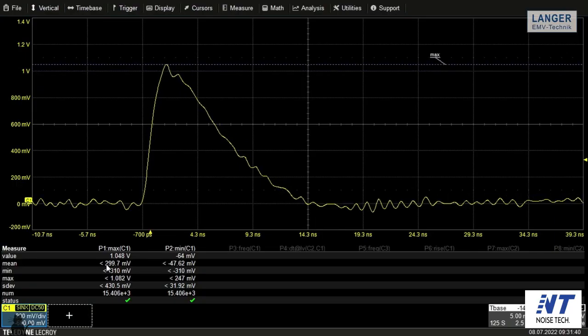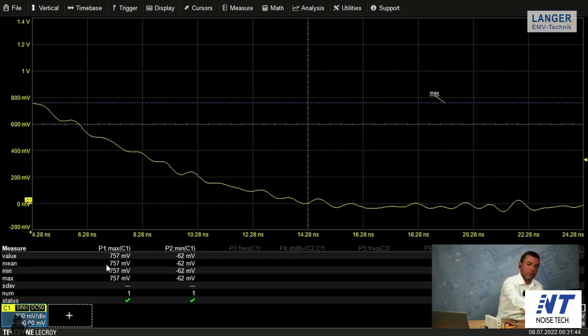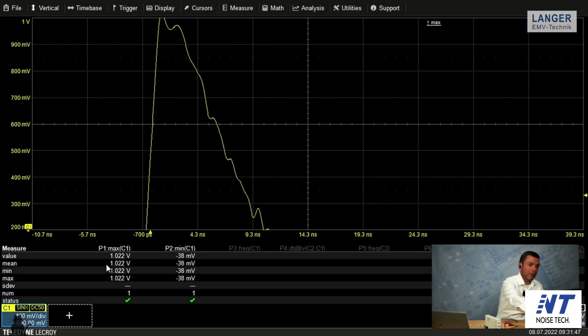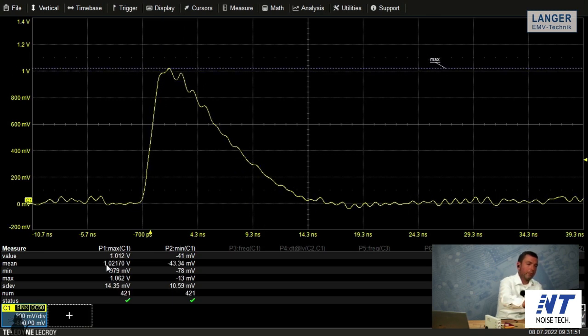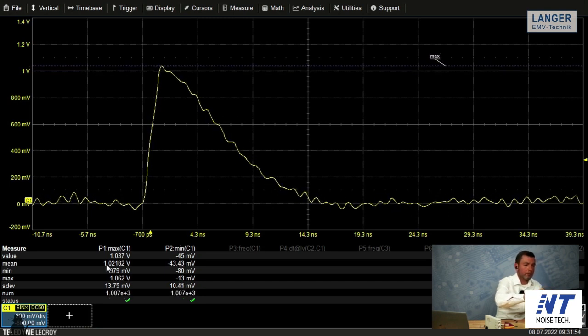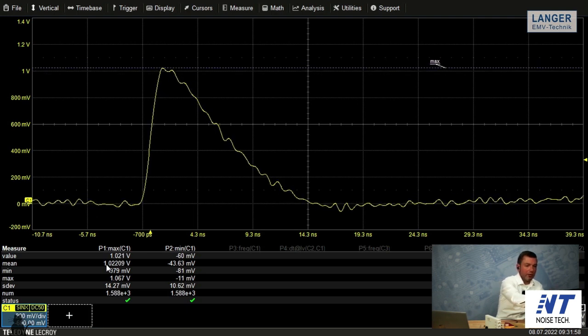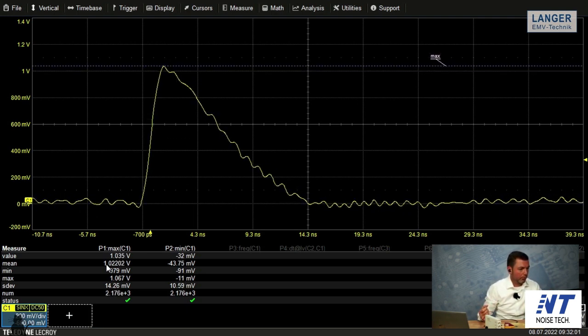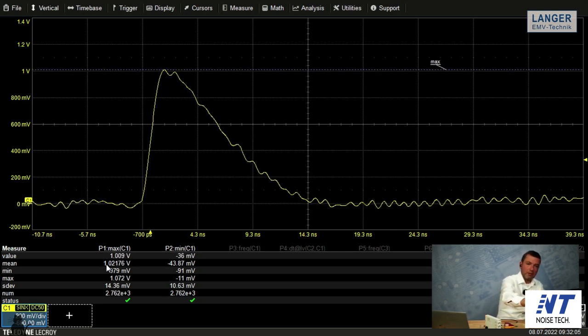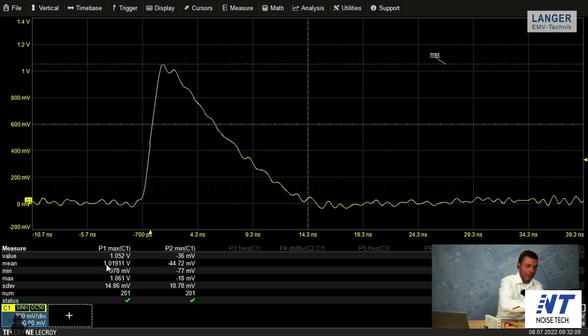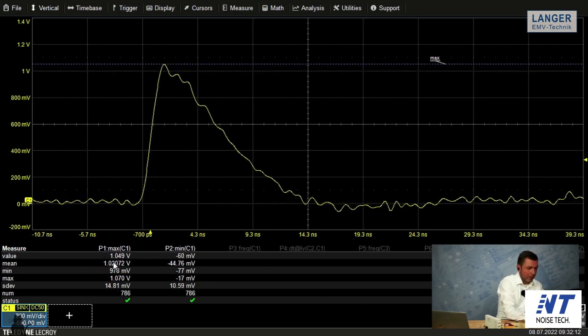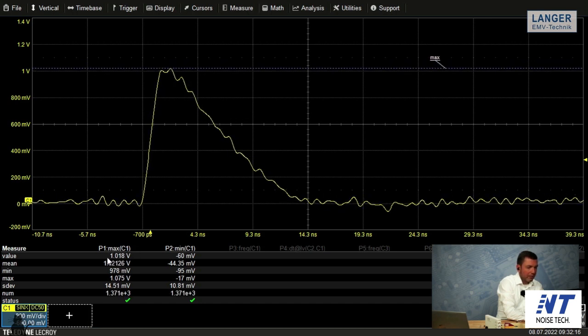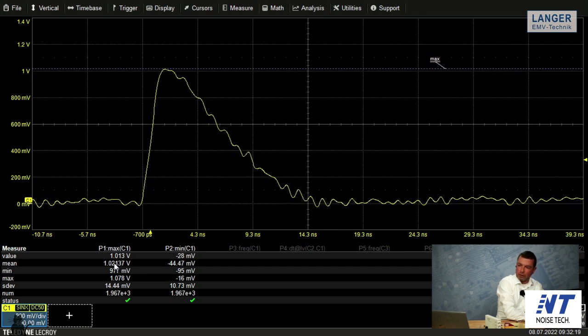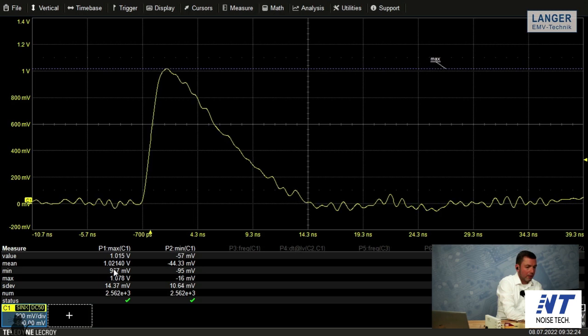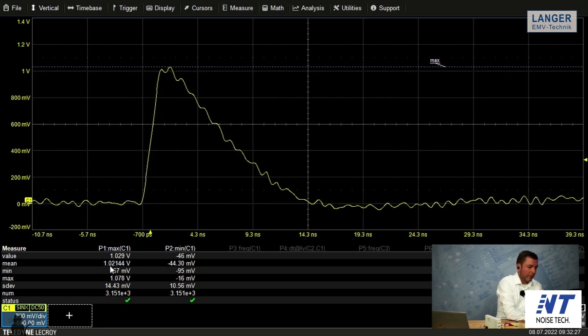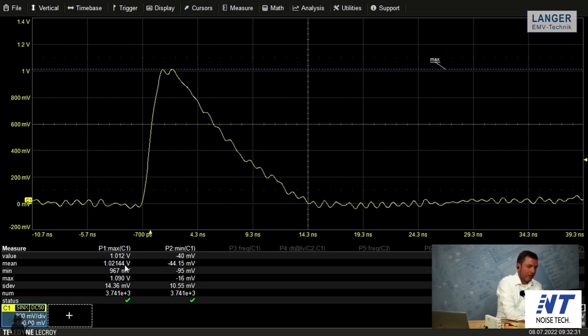Here on the oscilloscope, you have to change the vertical settings so that you have a minimum of 70% of the pulse in the measuring range of the oscilloscope. Then I clear my measuring sweeps, and now you can see here the actual measured value, and that's the mean value. I set in the software a 1 volt positive pulse level, and now you can see it's 1.02 volt. So that's definitely good enough.